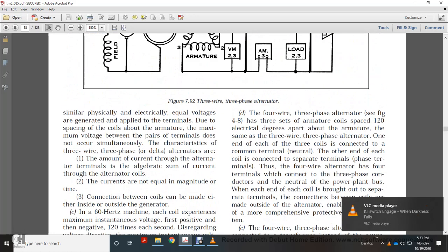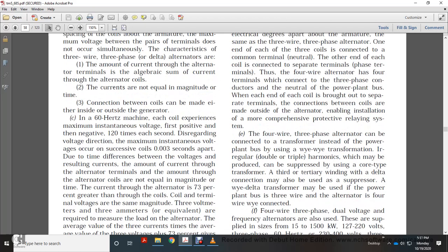There are also four-wire, three-phase alternators. See figure 4-8. Three sets of armature coils are placed 120 electrical degrees apart on the armature, the same as with the three-wire, three-phase alternator. One end of each of the three coils is connected to a common terminal, the neutral, with the other ends of the coils connected to separate terminals. The four-terminal alternator is connected to the three-phase conductors and the neutral of the power plant bus. When each end of each coil is brought to a separate terminal, the connections between the coils are made outside of the alternator, enabling installation of a more comprehensive protective relaying system.